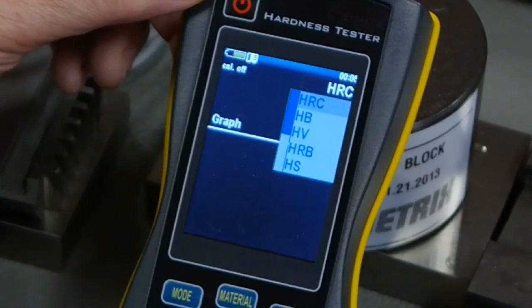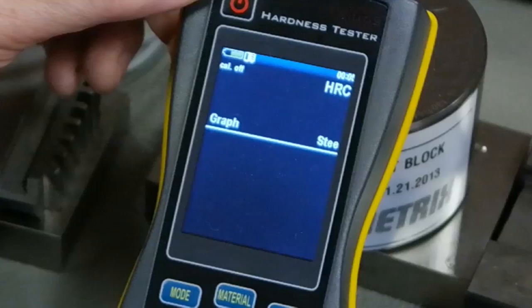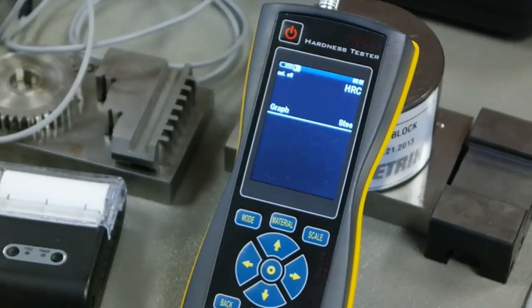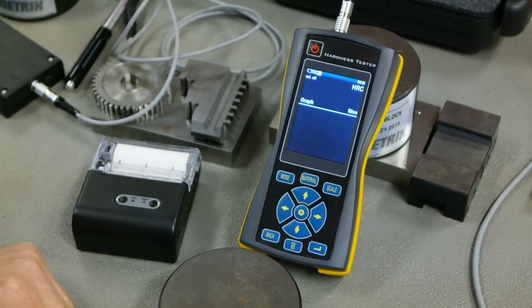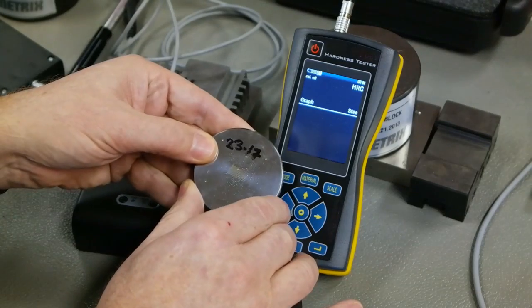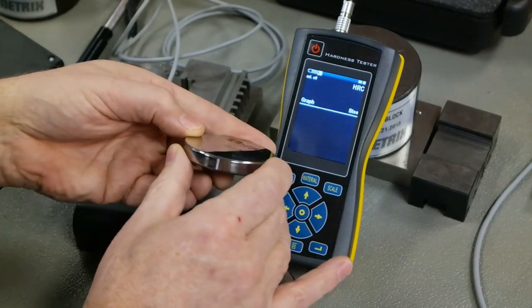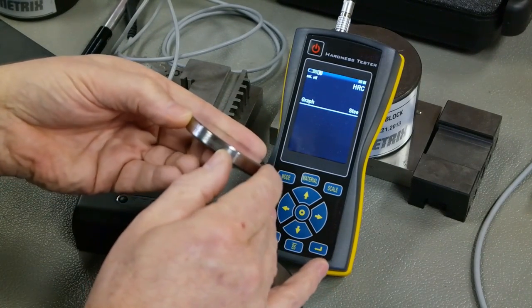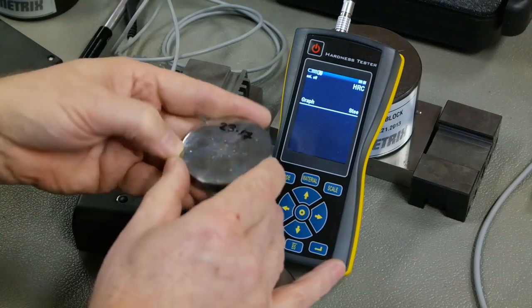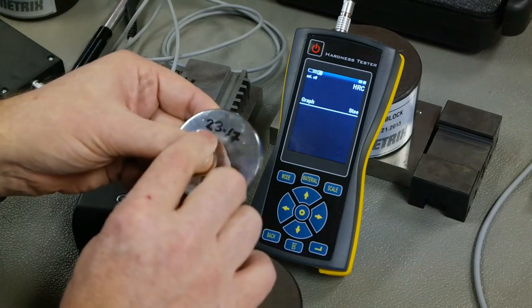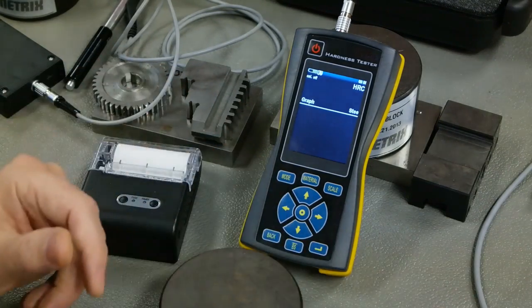So we're working here in HRC, and what I'm going to do now is to show you just how super accurate these devices are. Here I have a NIST traceable test block. This has a tolerance on it of plus or minus 1 HRC, and the hardness is 23.17.